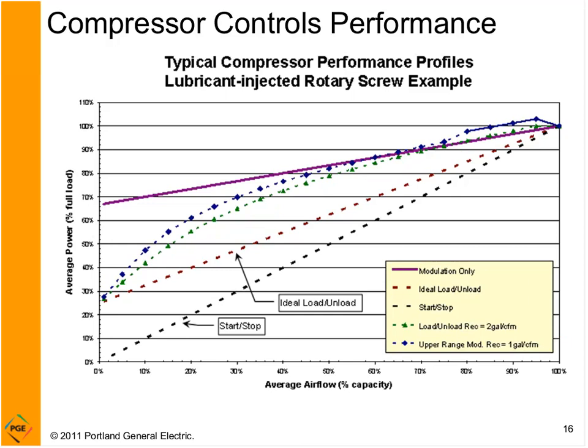A hybrid approach combines upper-range modulation with blow-down: I throttle back to a certain point, reach a pressure, then blow down. This yields a better average curve. The no-load power, when fully unloaded and just idling, can vary between 15% and 30% depending on the manufacturer. Some compressors maintain sump pressure, which keeps the power a little higher.